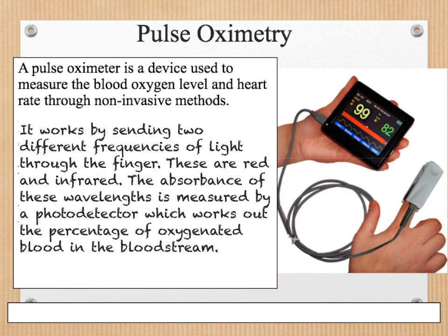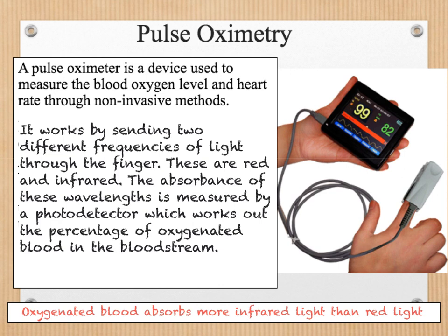We also need to be aware of pulse oximetry. A pulse oximeter is a device used to measure the blood oxygen level and heart rate through a non-invasive method — we can see it clips onto the finger. It works by sending two different frequencies of light through the finger: red and infrared. The absorbance of these wavelengths is measured by a photodetector. Oxygenated blood absorbs more infrared light than red light, whereas deoxygenated blood absorbs more red light than infrared light. We can use this information to determine the level of oxygenated blood in the body, and depending on the ratio of red to infrared light picked up by the photodetector, we can work out the saturation of oxygen in the blood.